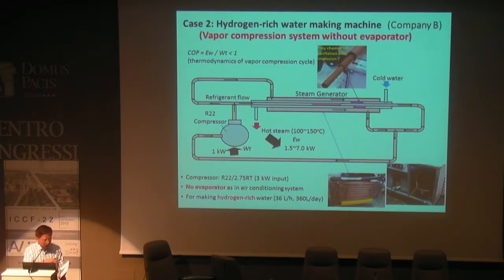The machine, as a compressor, gets high pressure, high temperature refrigerant vapor, then goes through what I call a steam generator. The water coming in is cold water, 25 degrees, then heated up to about 150 or 160 degrees, is steam, and then comes out. And there's no evaporator. So by energy conservation, thermodynamics, COP should be less than 1, but it is not.